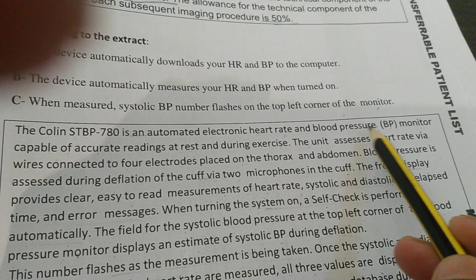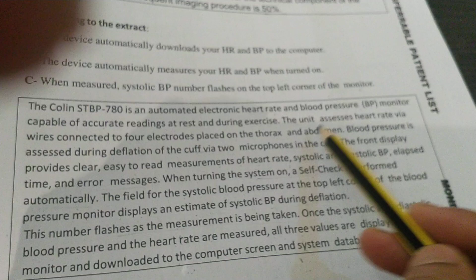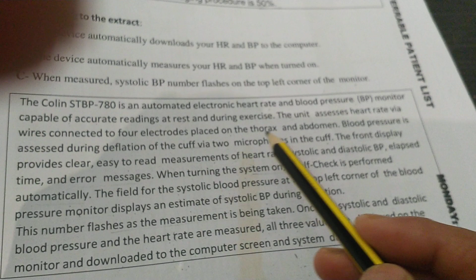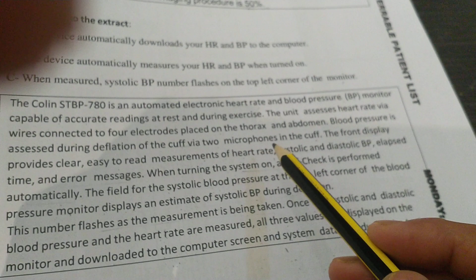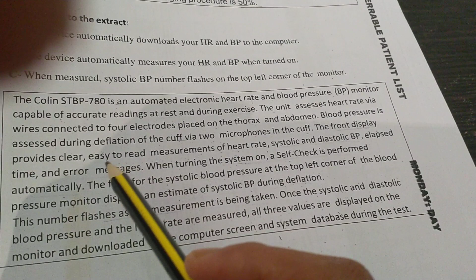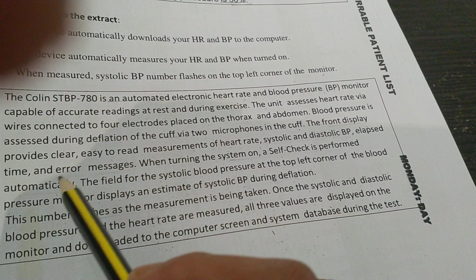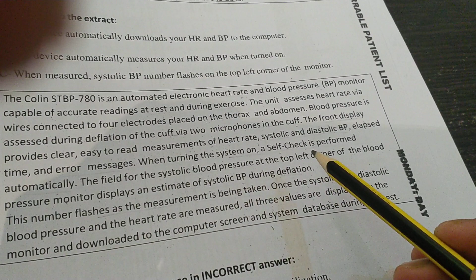Then the extract 5. The Colin STBP 780 is an automated electronic heart rate and blood pressure monitor capable of accurate readings at rest and during exercise. The unit assesses heart rate via wires connected to 4 electrodes placed on the thorax and abdomen. Blood pressure is assessed during deflation of the cuff via 2 microphones in the cuff. The front display provides clear, easy to read measurements of heart rate, systolic and diastolic BP, elapsed time and error messages. When turning the system on, a self-check is performed automatically.